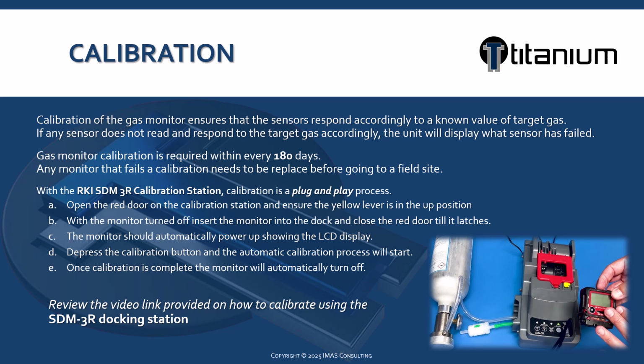With the RKI SDM-3R calibration station, calibration is a plug-and-play process. Open the red door on the calibration station and ensure the yellow lever is in the up position. With the monitor turned off, insert the monitor into the dock and close the red door till it latches. The monitor should automatically power up. Depress the calibration button and the automatic calibration process will start. Once calibration is complete, the monitor will automatically turn off. Review the video link provided on how to calibrate using the SDM-3R docking station.